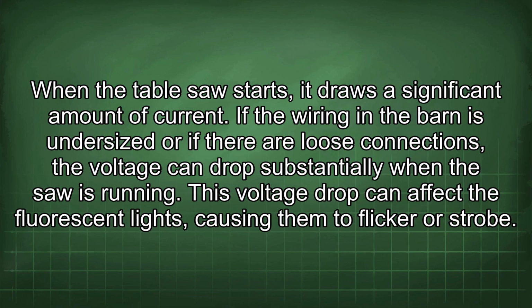When the table saw starts, it draws a significant amount of current. If the wiring in the barn is undersized or if there are loose connections, the voltage can drop substantially when the saw is running. This voltage drop can affect the fluorescent lights, causing them to flicker or strobe.